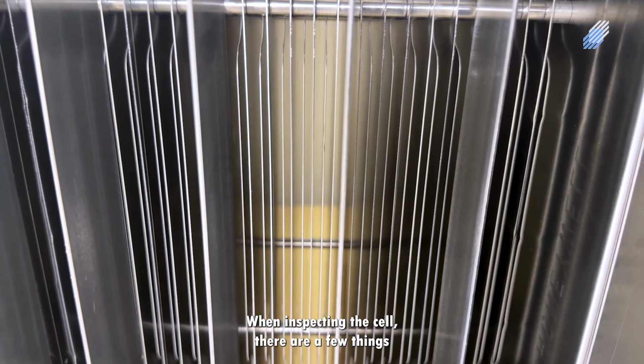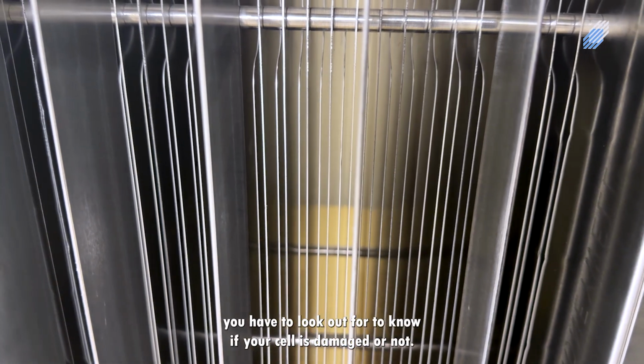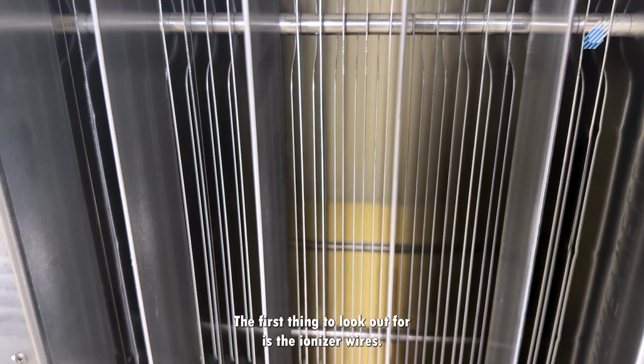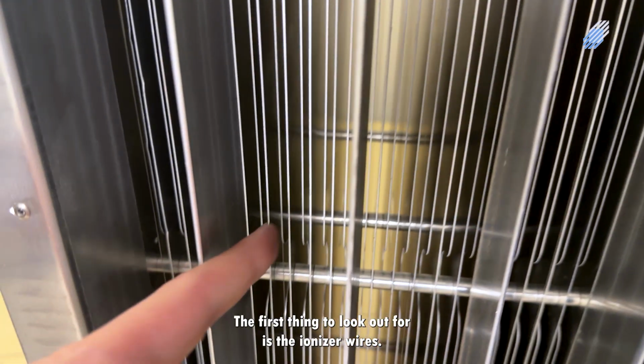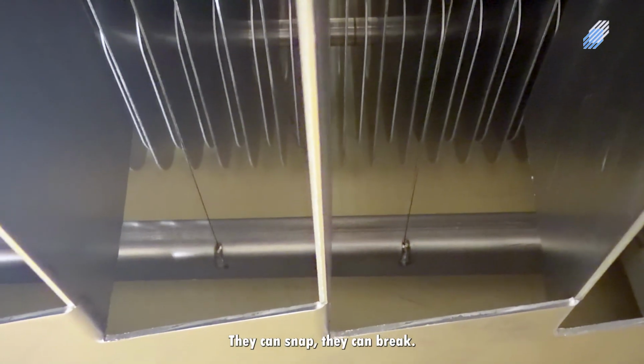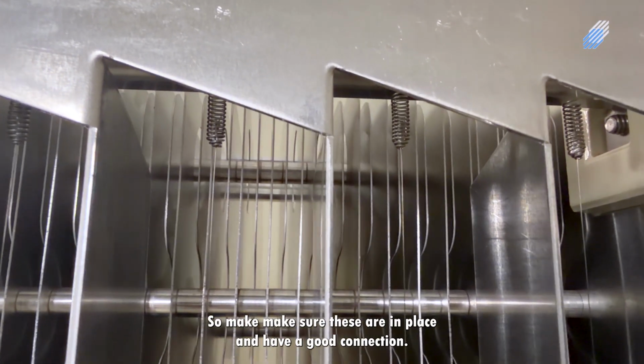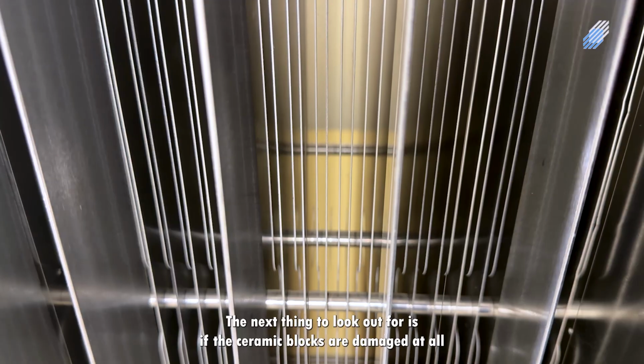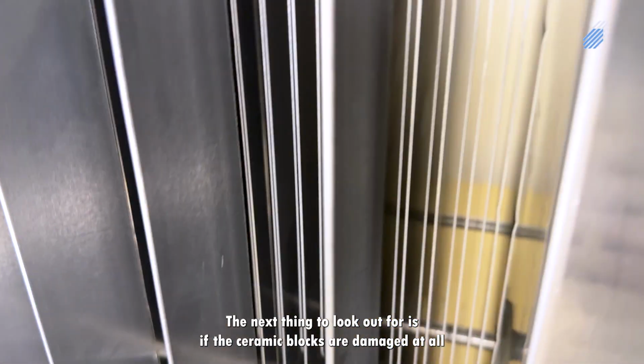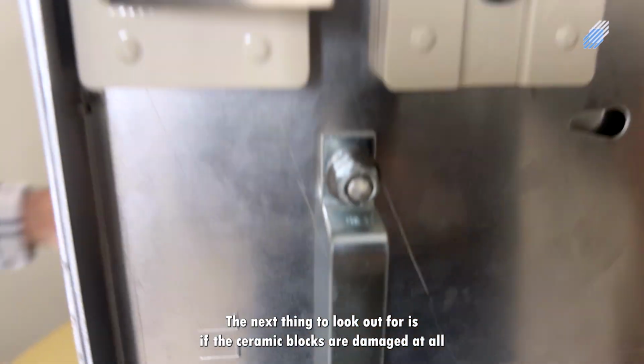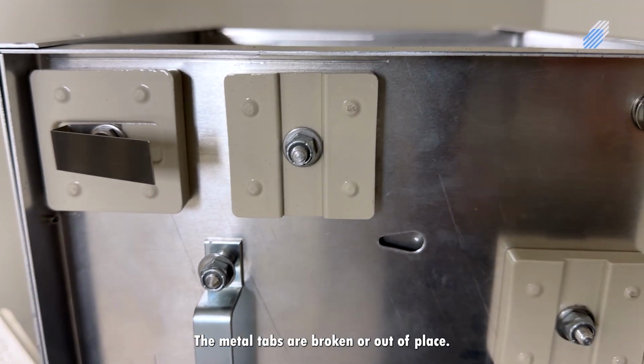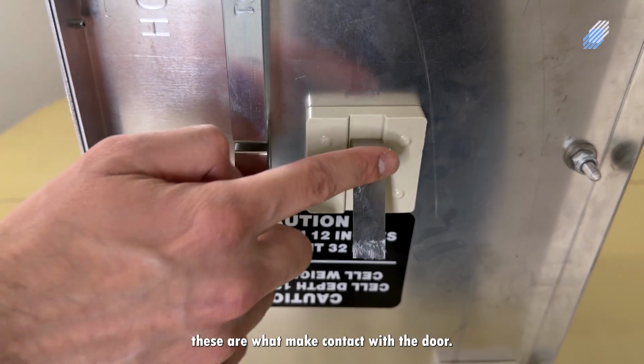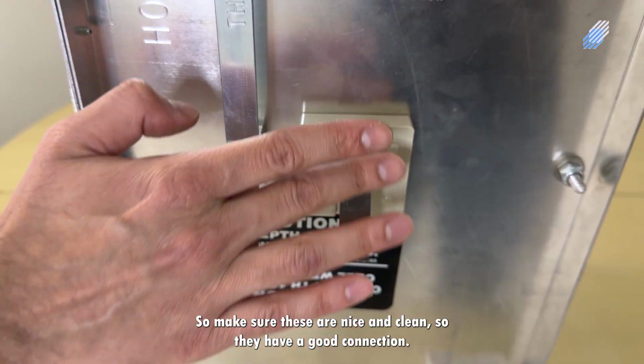When inspecting the cell, there are a few things you have to look out for to know if your cell is damaged or not. The first thing to look out for is the ionizer wires. These can come out of place, they can snap, they can break, so make sure these are in place and have a good connection. The next thing to look out for is if the ceramic blocks are damaged at all, if they're cracked, or the metal tabs are broken or out of place.